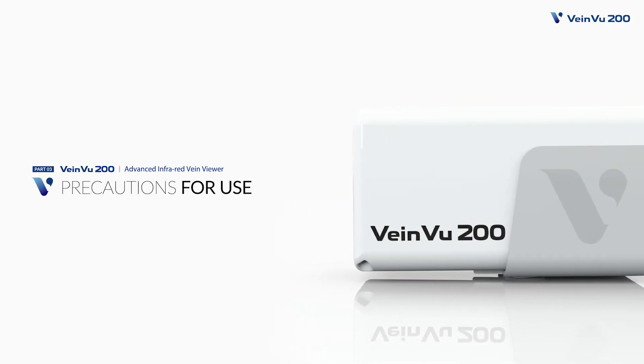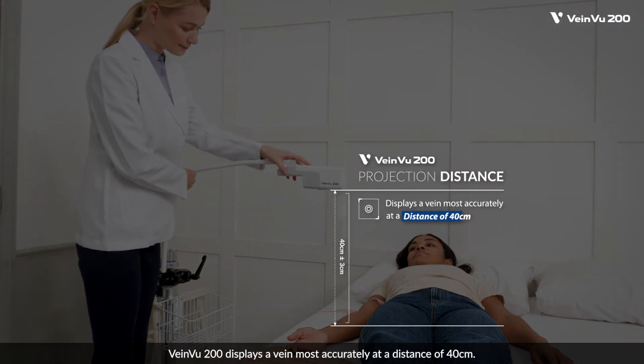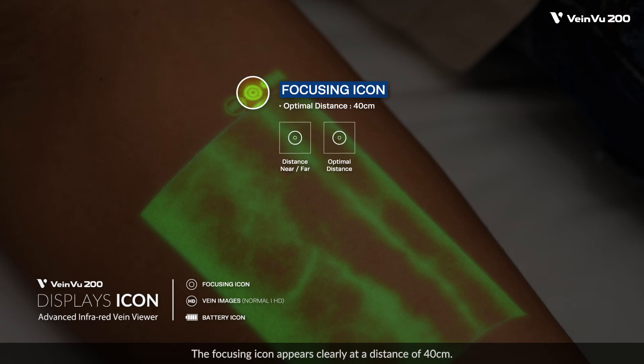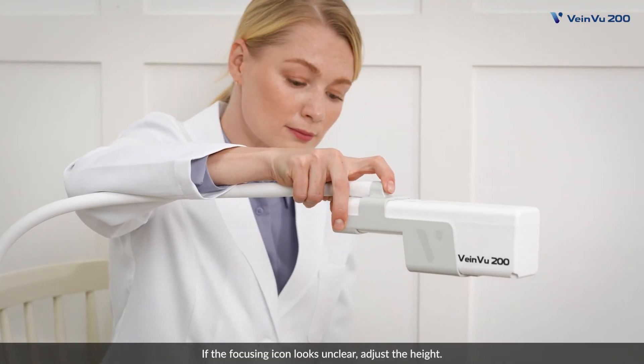Precautions for use: VeinVu 200 displays a vein most accurately at a distance of 40 centimeters. The view image displays a battery icon and a focusing icon to show distance. The focusing icon appears clearly at a distance of 40 centimeters. If the focusing icon looks unclear, adjust the height.